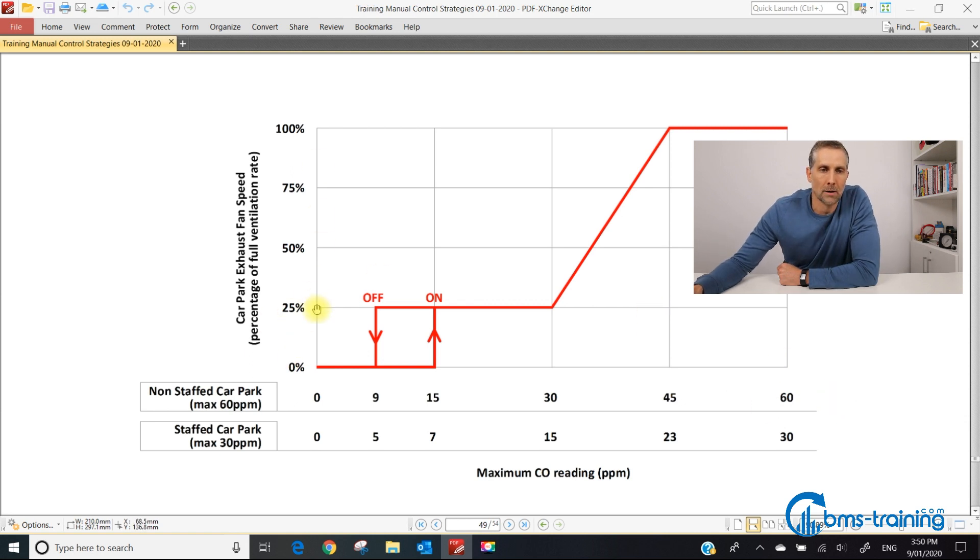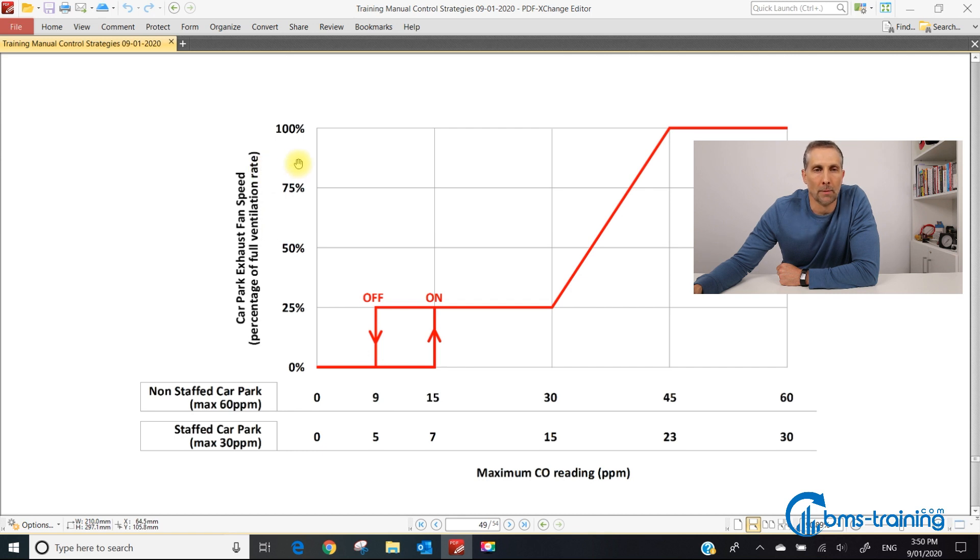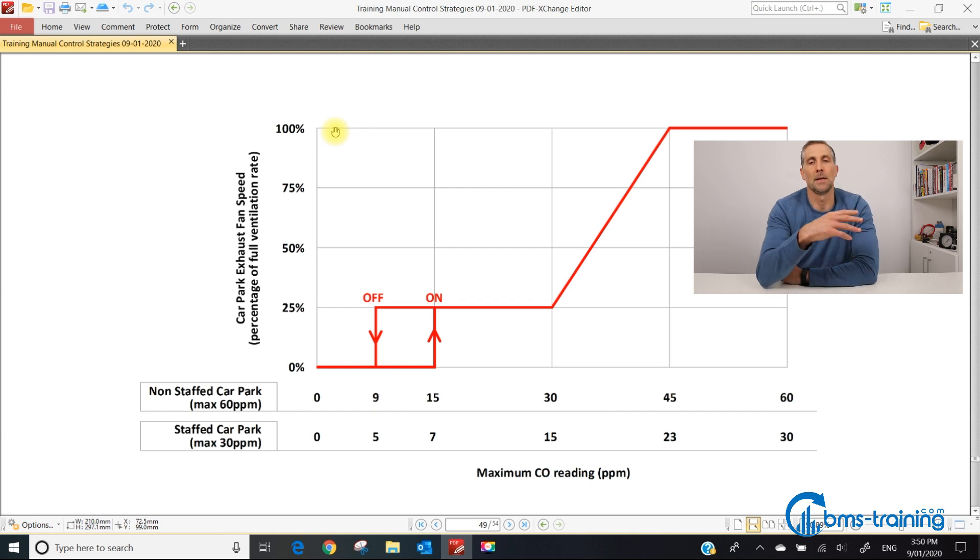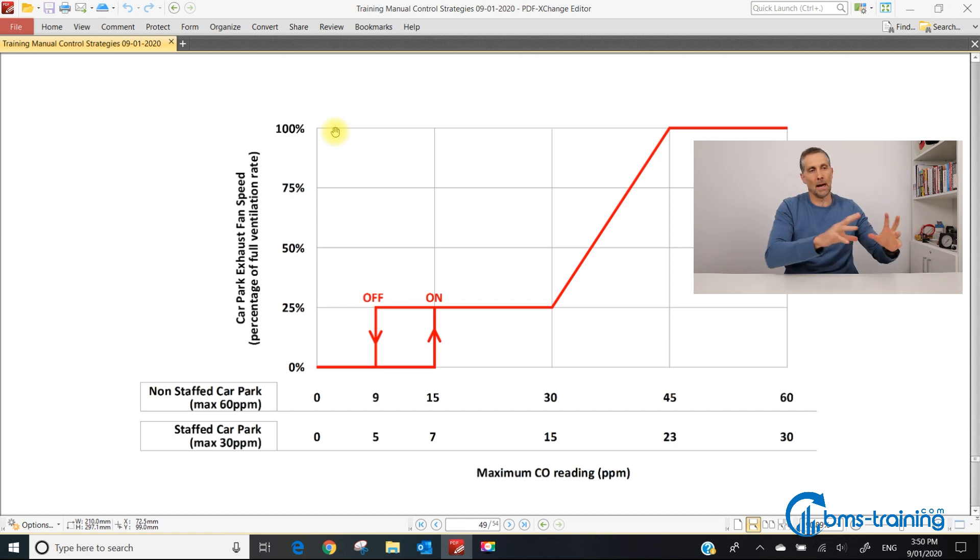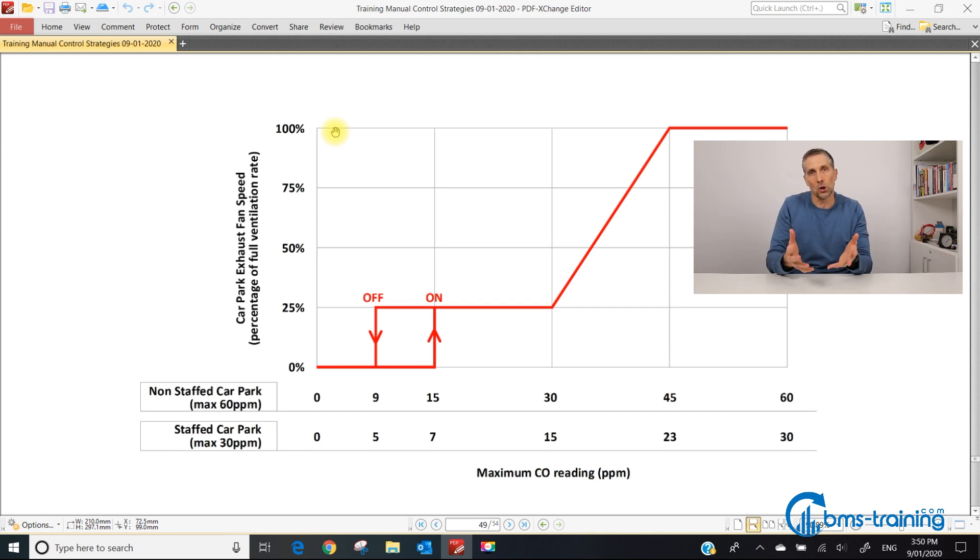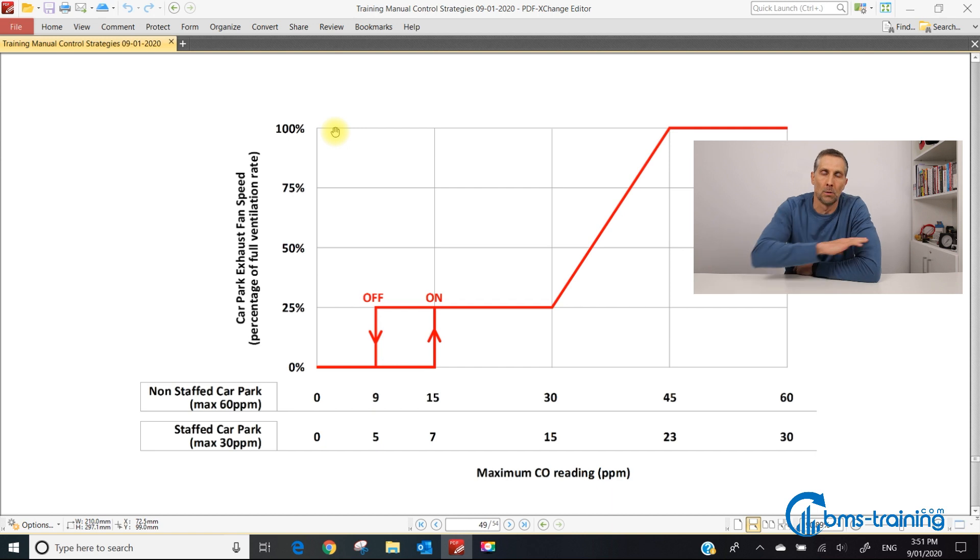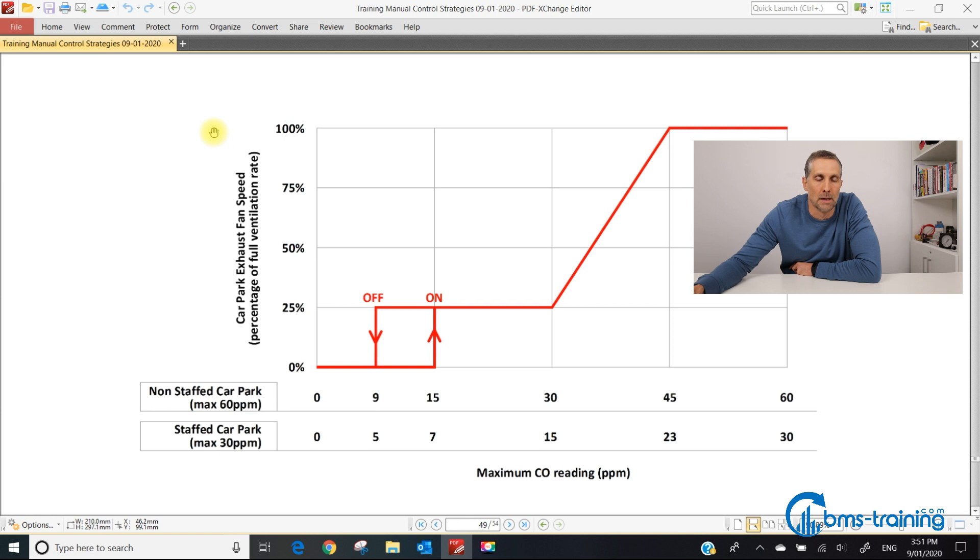On the y-axis we have the car park exhaust fan speed, 0 to 100%, but it's actually the percentage of full ventilation rate. When the mechanical commissioning technician did the balancing, if the exhaust fan runs at say 95% at designed ventilation rate, you would increase this up to 95%. It's a description of fan speed but not exactly the fan speed in many cases.